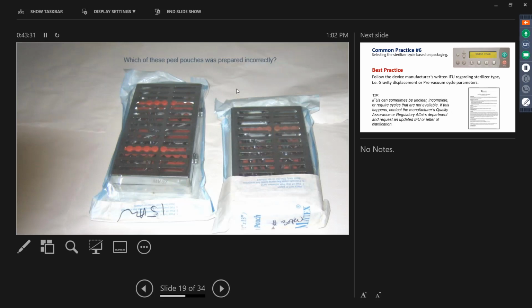Which one of these peel pouches is prepared incorrectly? It's kind of obvious to me. Is it the one on the left or the one on the right? The one on the right is incorrect. This is common practice. You see what they've done? They've got a peel pouch that's really not, it's oversized. They just do this. That's a violation of best practice.